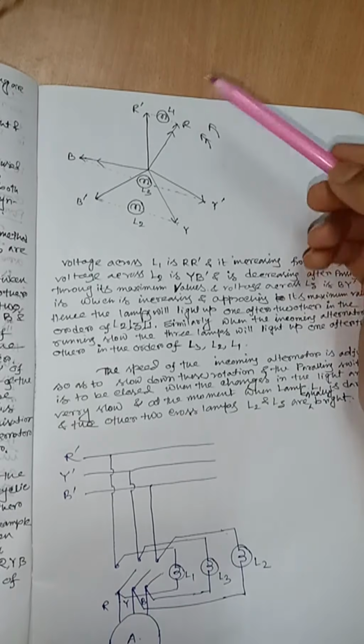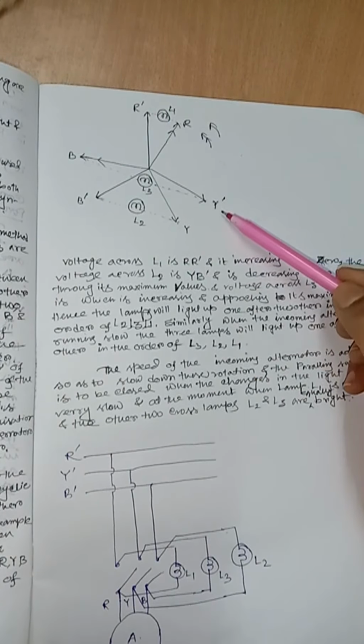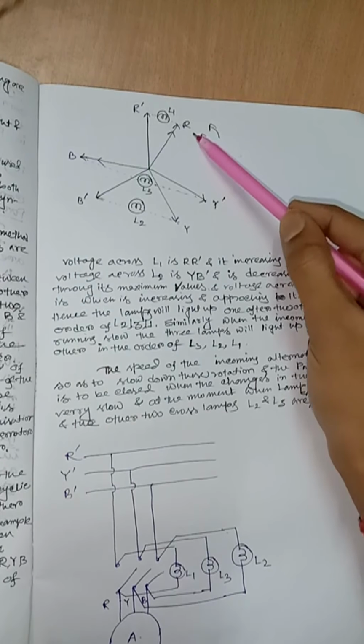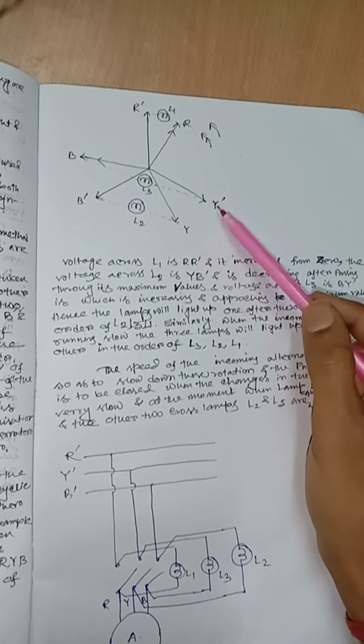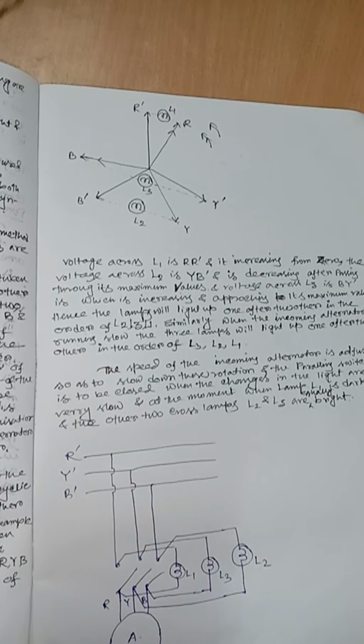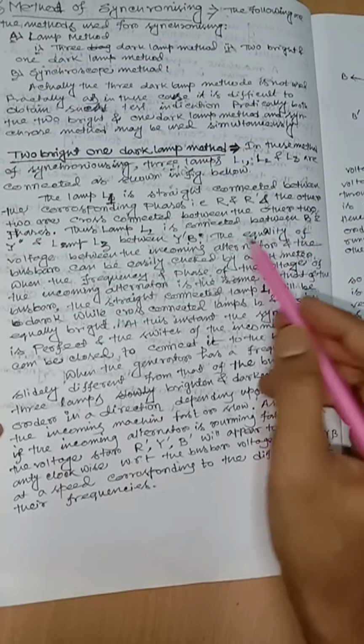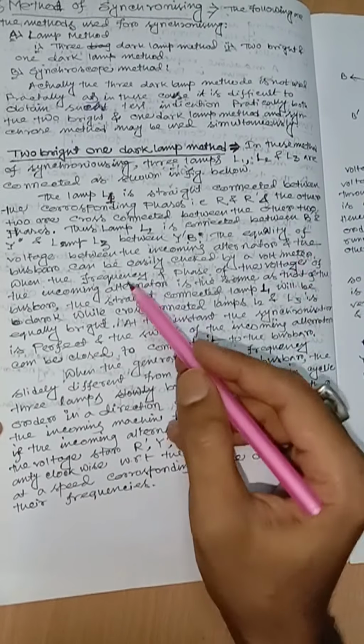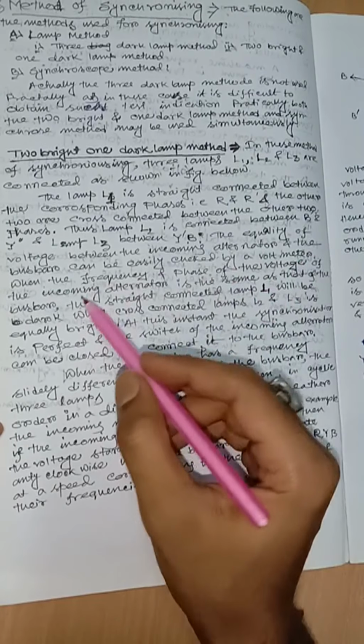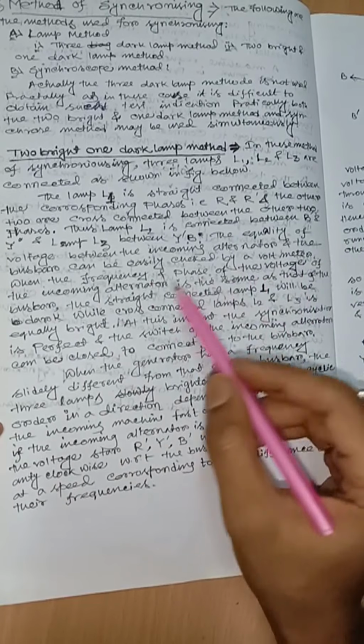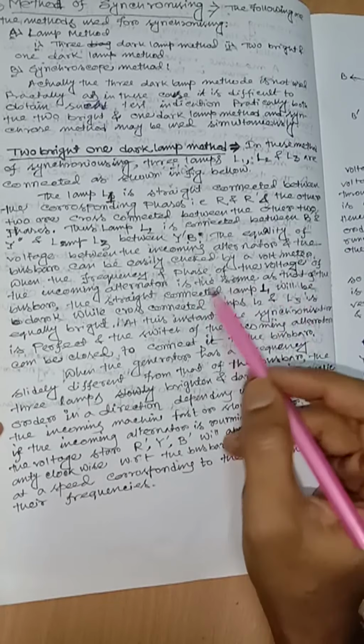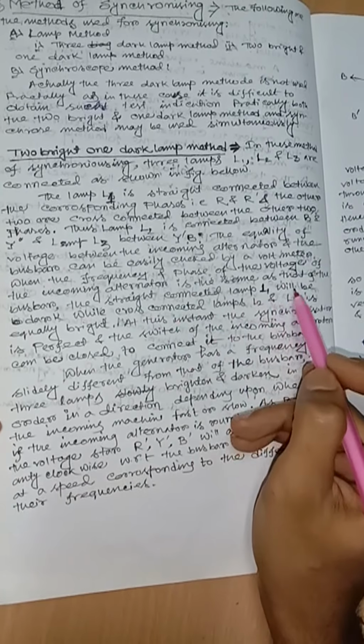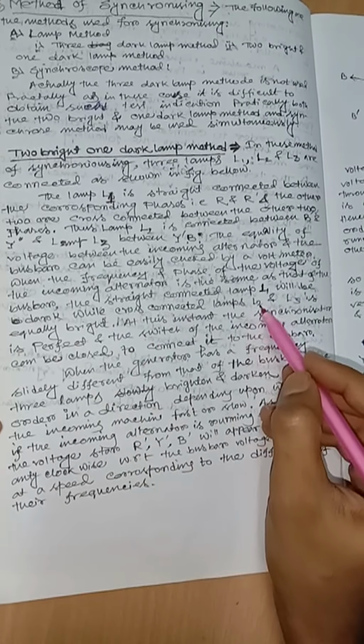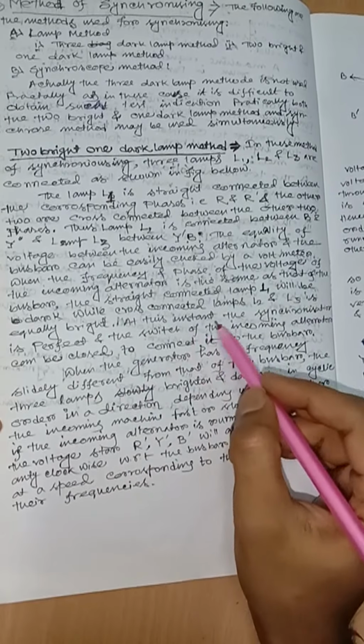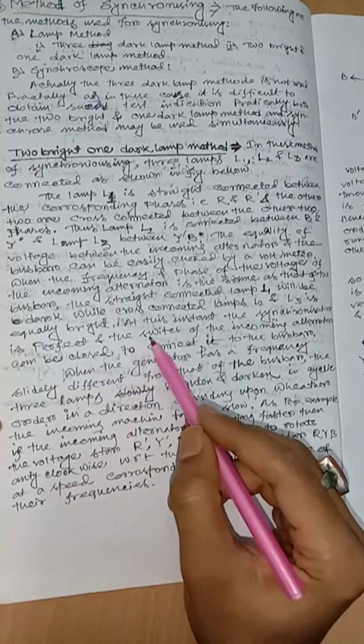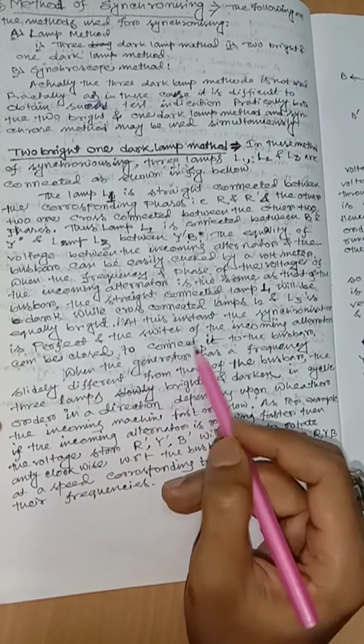In this phasor diagram, R dash, B dash, Y dash represent our bus bar voltage, and the phasor R, B, Y represents our incoming alternator voltage. Now the equality of voltage between the incoming alternator and the bus bar can be easily checked by a voltmeter. When the frequency and phase of the voltage of the incoming alternator are the same as those of the bus bar, the straight connected lamp L1 will be dark, while the cross connected lamps L2 and L3 are equally bright. At this instant, the synchronization is perfect, and the switch of the incoming alternator can be closed to connect it to the bus bar.